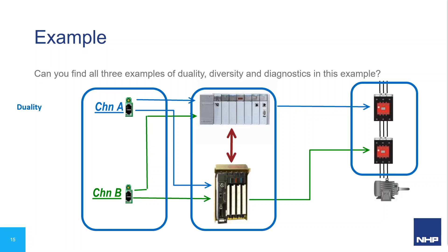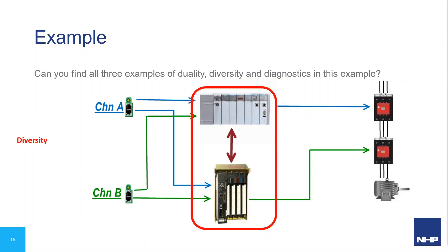For duality, we have two switches running in parallel, two logic controllers, and two contactors — a single failure in any one does not result in losing the entire system. For diversity, we're using two different types of logic controllers, each performing the same function but from completely different series, so a fault inherent in the design of one does not necessarily exist in the other.